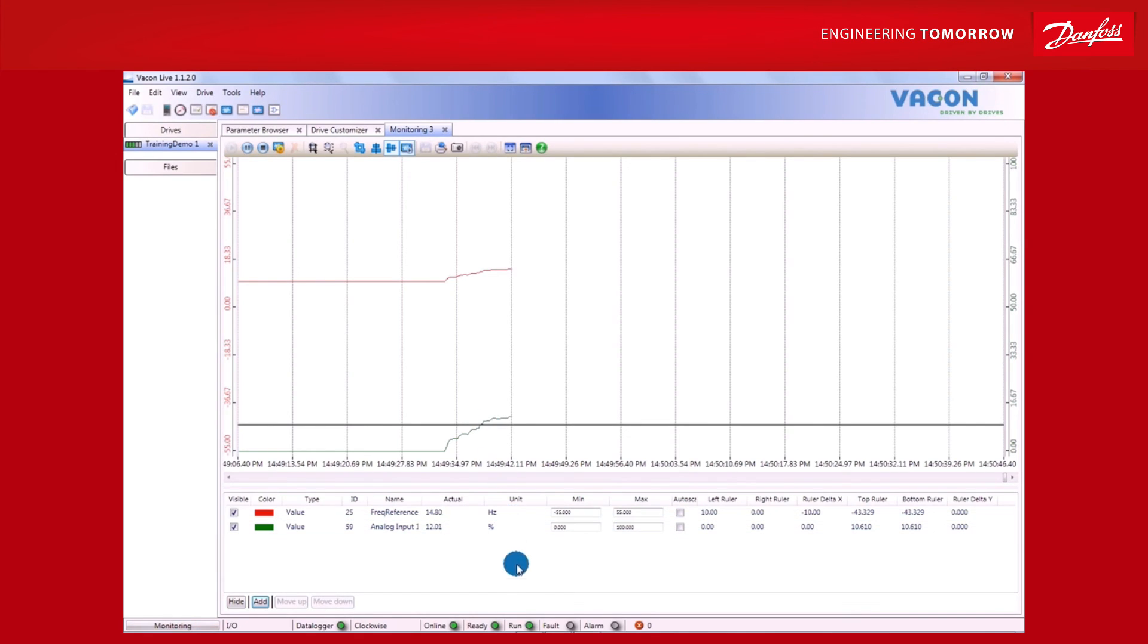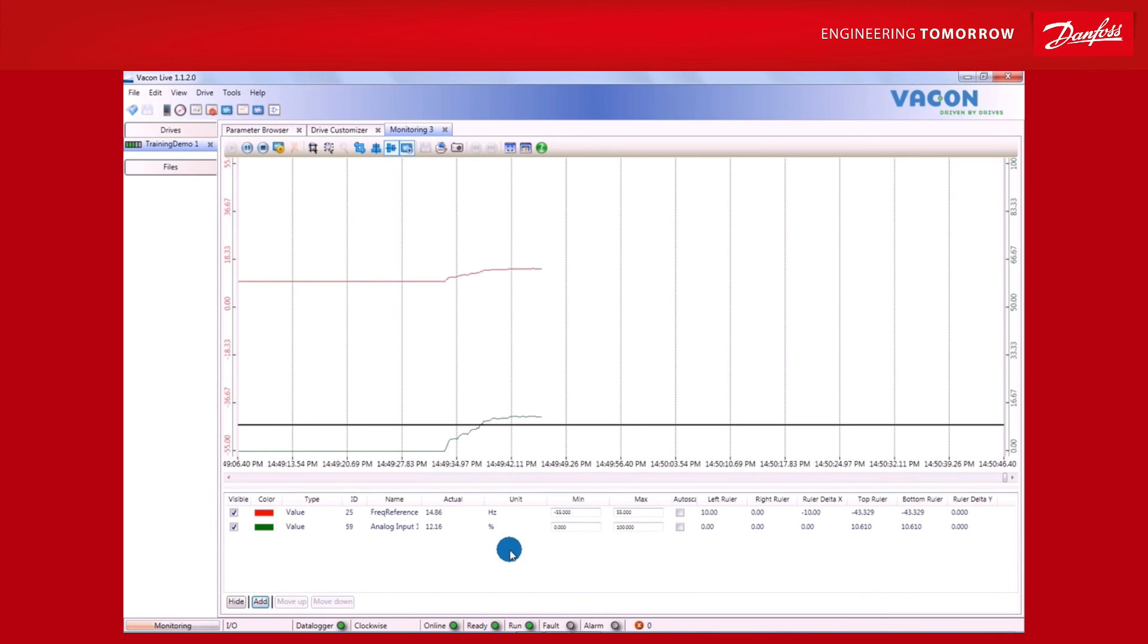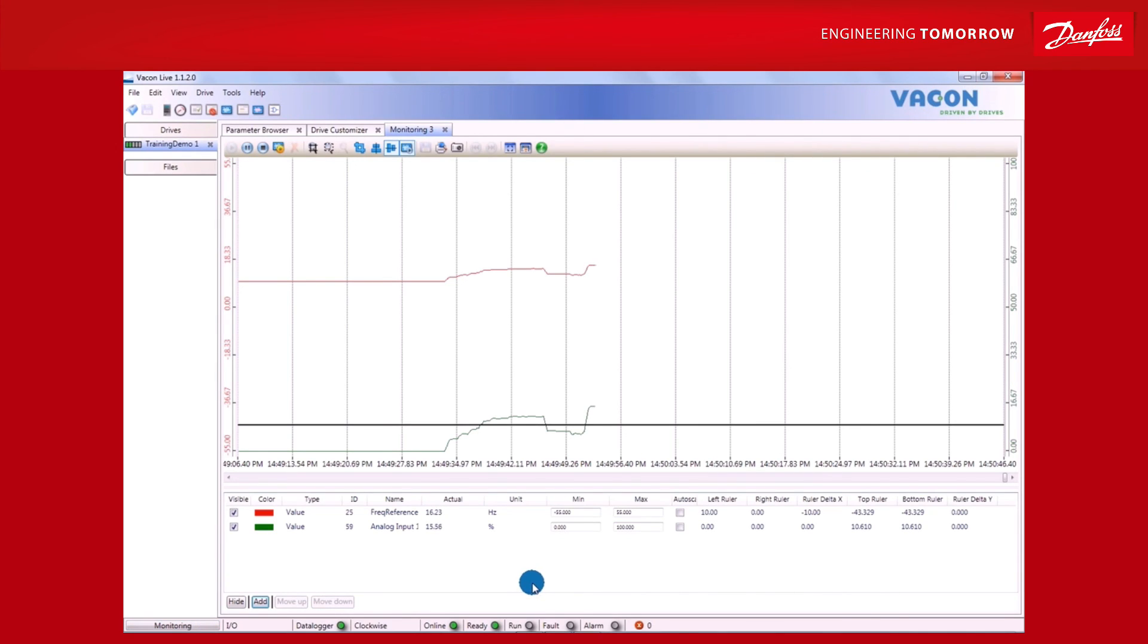However, when it reaches that 10% level, the value which is being monitored, analog input 1 in this case, turns green, and we start to feed a frequency reference to the motor, so that it is turning. When the frequency drops below that level, the motor stops.